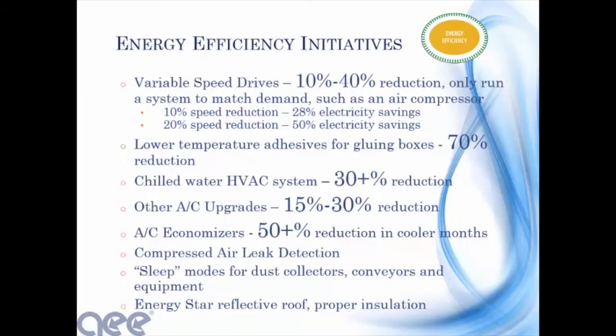Variable speed drives. I had heard a lot about variable speed drives. I didn't quite understand where the energy savings come from. But according to what's called the affinity laws, the energy that a motor consumes is proportional to the cube of its speed. So if you slow down a motor by just 10%, the energy consumed would be 90% times 90% times 90%. So you only use 72% of the electricity to run a motor at 90% of its speed. And so likewise, if you could slow it down to 80%, you're cutting the electricity in half.